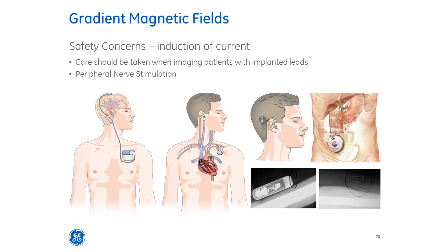So why does Faraday's law of induction matter in MRI? Consider all of the possibilities of looping in the body. This could be a wire, it could be the looping of the cables, it could even be the looping of extremities by simply folding your hands across your abdomen, thus making a loop of human tissue. No matter how or what it's made of, a conducting loop that is exposed to a varying magnetic field has a potential to induce a current.